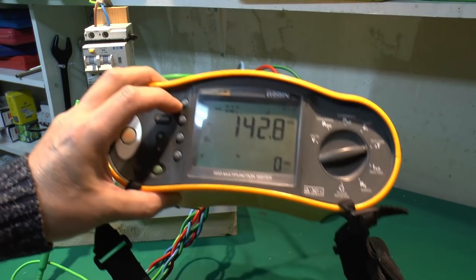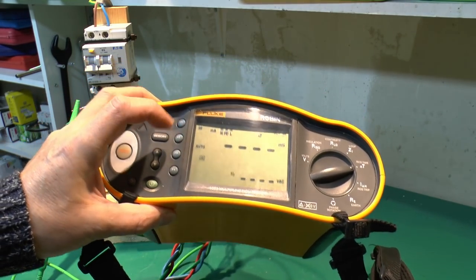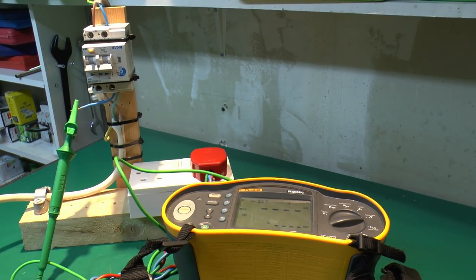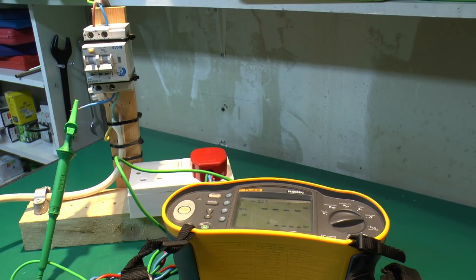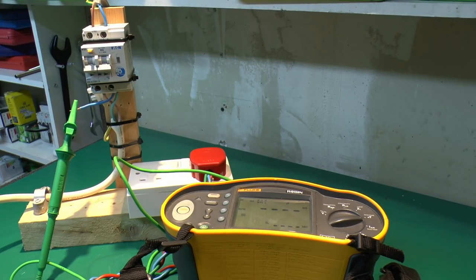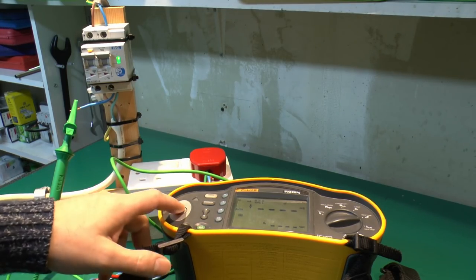So if we just go to auto, that will cycle through the six tests and we'll need to reset the device obviously between. So it's going to test half on the 0 and 180, 1 on the 0 and 180, and times 5 on the 0 and 180 as well. So half the current is going to be 15mA. In this case, this is a 30mA deal. Times 1 is the 30mA, and the times 5 of course is 150mA. And the 0 and 180 refers to the point in the AC waveform where the thing actually trips. And of course that can affect the tripping time, because it depends on where it's going to trip on the particular cycle. So where the fault occurs can have some impact on the actual trip time. So same connections as we had previously. And if we turn on...